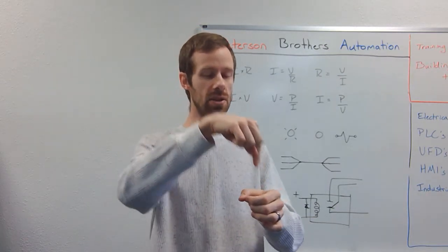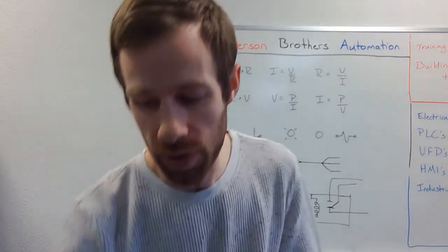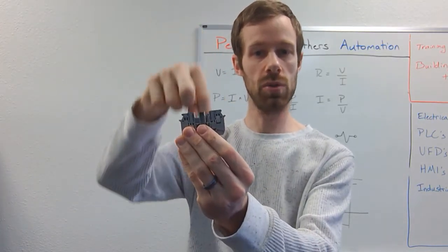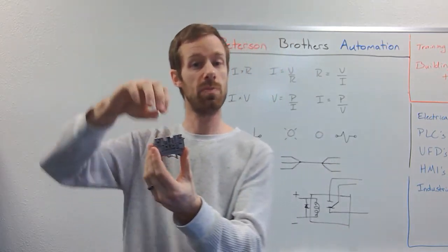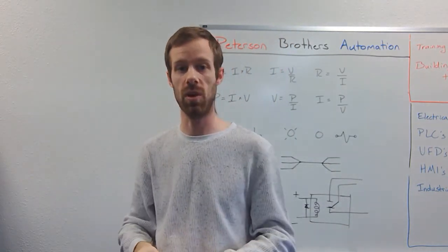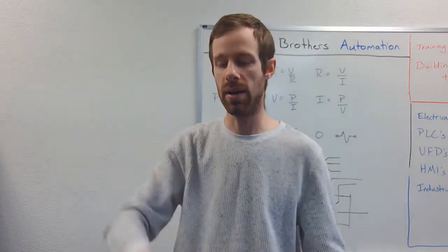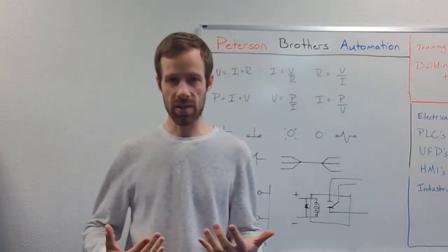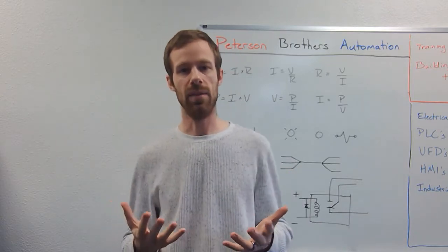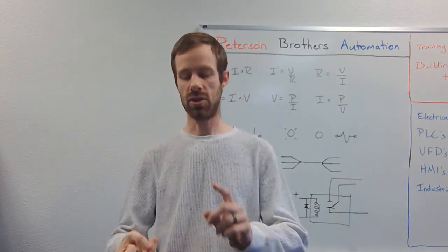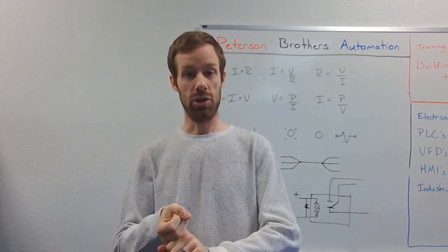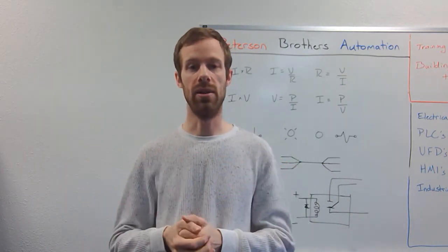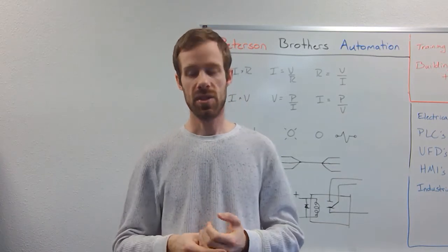If each one gets its own separate screw, like it does with a setting on a terminal block, every wire gets its own screw terminal. You can tighten down every one of them and properly torque it down no matter what size the wire is. It's going to be way better, way more accurate in the long run. So there's a lot of ways to indicate that we have a parallel circuit: wire nuts, terminal blocks with jumpers making terminal strips, and sometimes seeing multiple wires, at least 3, stuck under the same place.